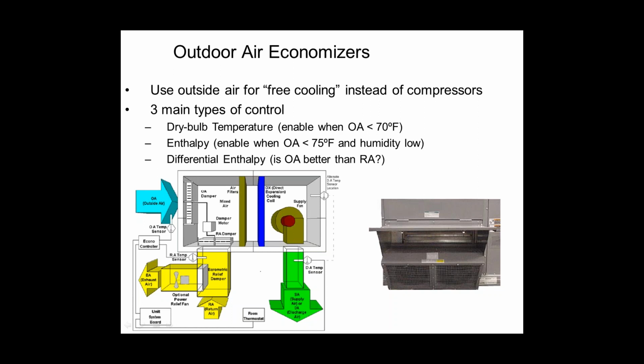The code actually requires 70. So what does that mean? That means if you want to cool the space and the outdoor temperature is below 70 degrees, then you would open up the outside air damper and use the outside air to cool the space. Now, I know you can't cool most spaces with 70-degree air, but 70-degree air is probably better than whatever was going to come up the return duct, right, which was probably 75 or 78-degree air. So it's still better. So it'll help cool it some, and then you might have to have compressors assist it later on.